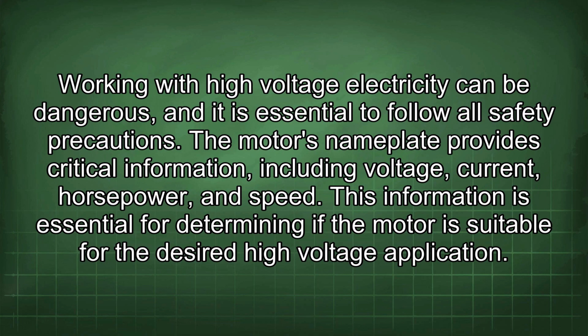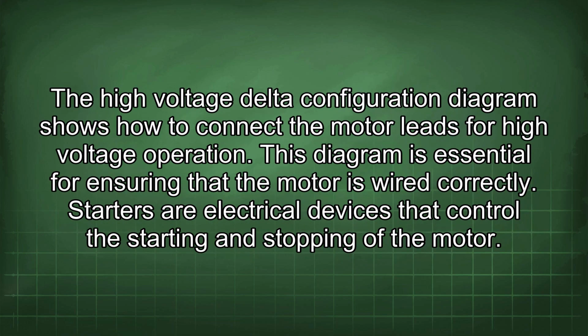The motor's nameplate provides critical information, including voltage, current, horsepower, and speed. This information is essential for determining if the motor is suitable for the desired high voltage application. The high voltage delta configuration diagram shows how to connect the motor leads for high voltage operation. This diagram is essential for ensuring that the motor is wired correctly.